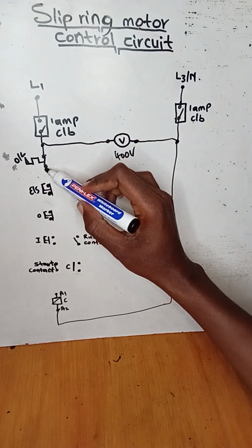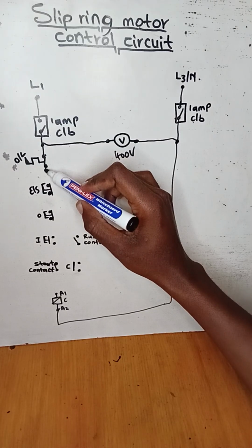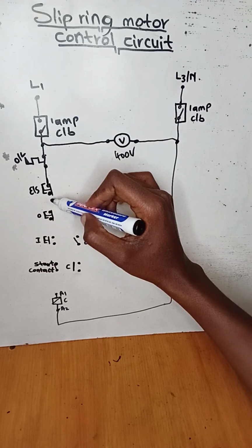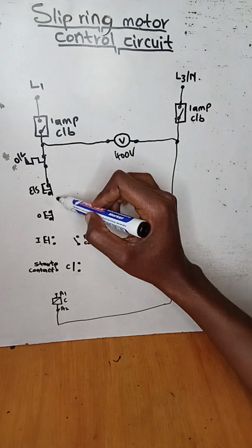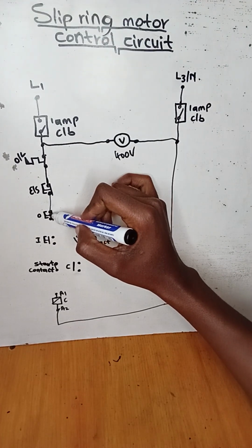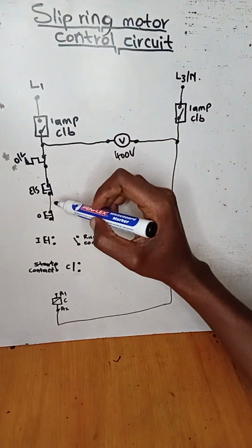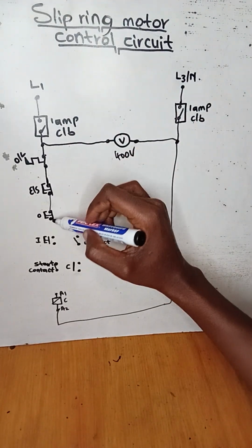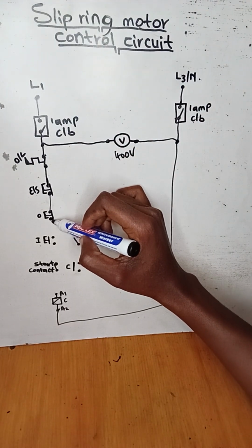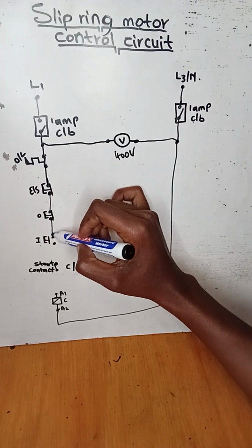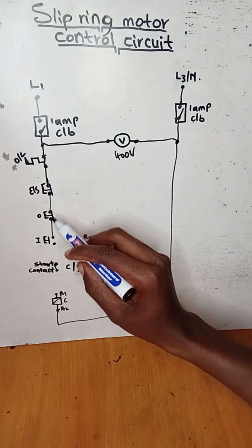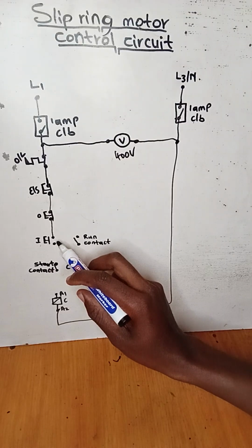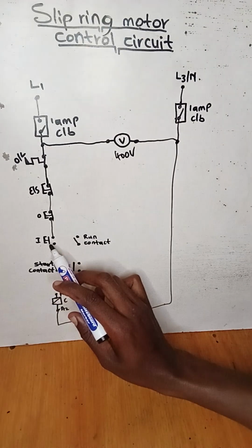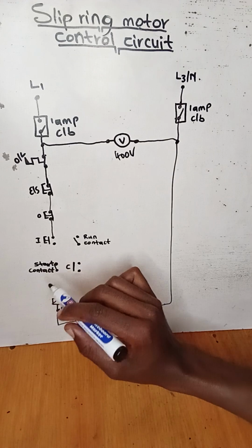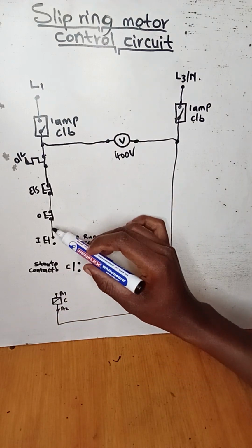closed contact, and the output will be connected to the in point of the emergency stop button, normally closed contact, and then the output will be connected to the in point of the stop button, normally closed contact, and then the output of the stop button will be connected to the in point of the normally open start button. Right?